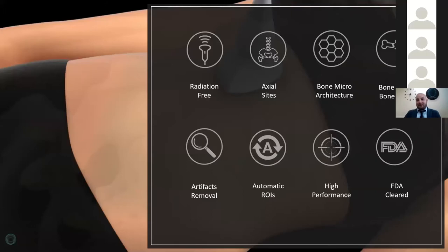Some advantages: well, Echo-S does not need a certified operator, no need for a shielded room because it's completely radiation free. The software automatically identifies the target bone interfaces within the sequence of the acquired signals and discards noisy acquisitions and artifacts, reducing the dependence on the operator and delivering highly reliable quantitative and qualitative measurements. Thanks to these very advanced features, R.E.M.S technology and Echolight devices obtained the FDA clearance as well as many other certifications from other countries in the world.